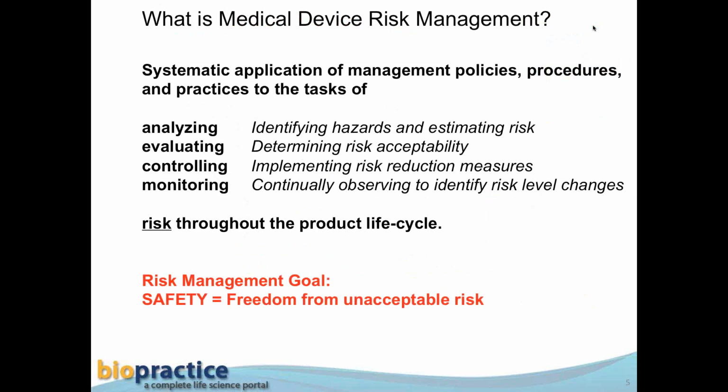So risk management, and today we're focused on medical device risk management, it's a product life cycle concept. So it's not something you just do once and you put it aside. You're supposed to be starting risk management at the input stage of product development and continuing it throughout the product life cycle. And again, risk analysis is just the first phase of risk management.